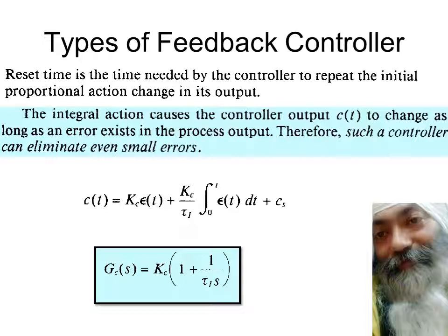So this kind of thing, when the controller output becomes more than what can be handled by the physical element, it goes beyond its fully opened position and then continues to pile up to 130, 140, 150 percent. And it has to come back, instead of coming from 100, it has to come back all the way from 150 to 140 to 130 and 120 and 100. By that time, things will be out of hand. So this kind of windup is called integral windup.